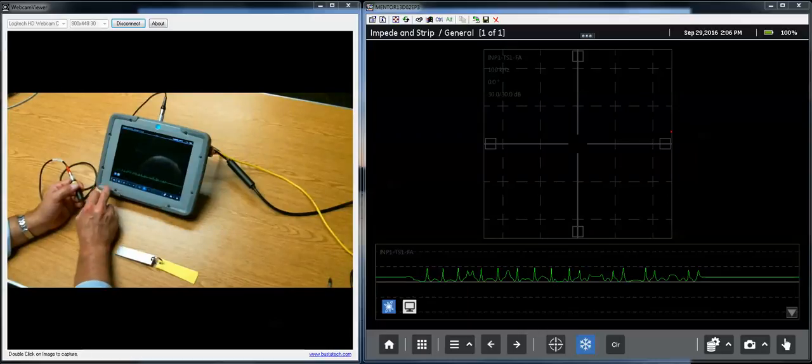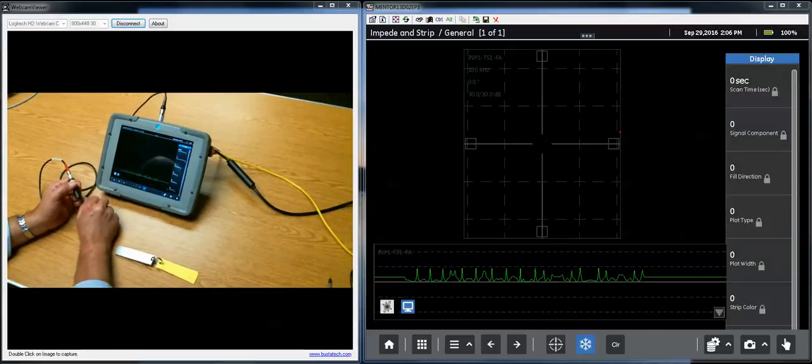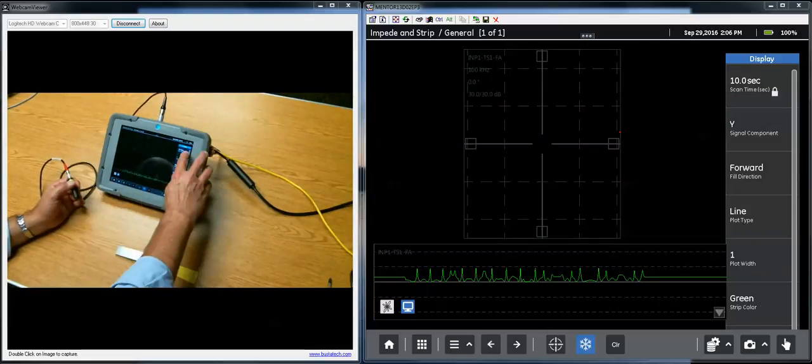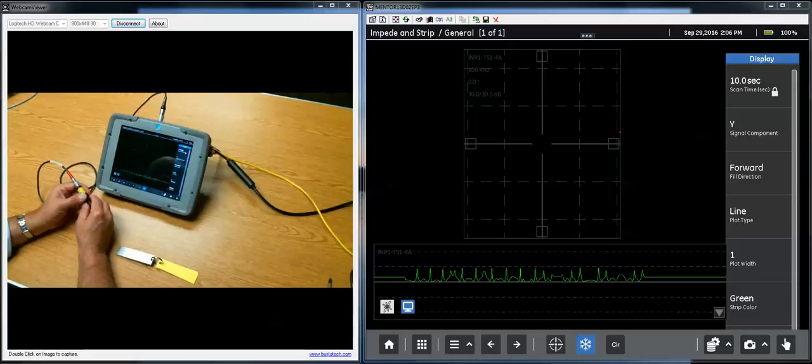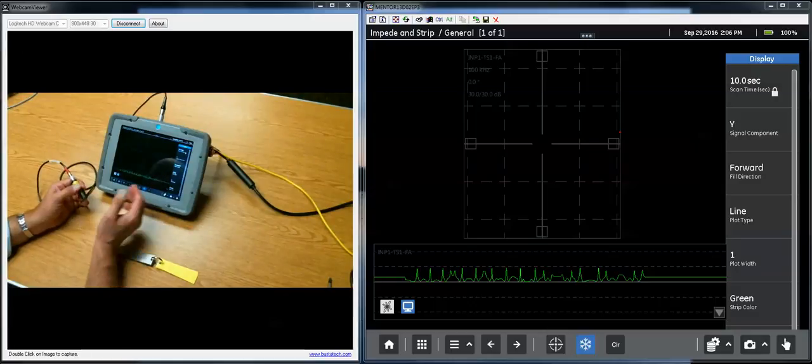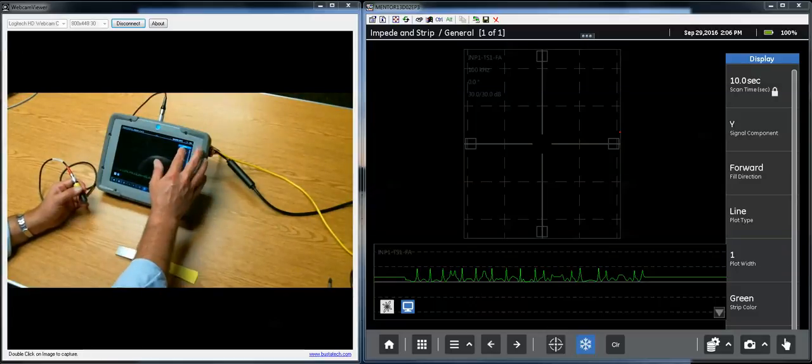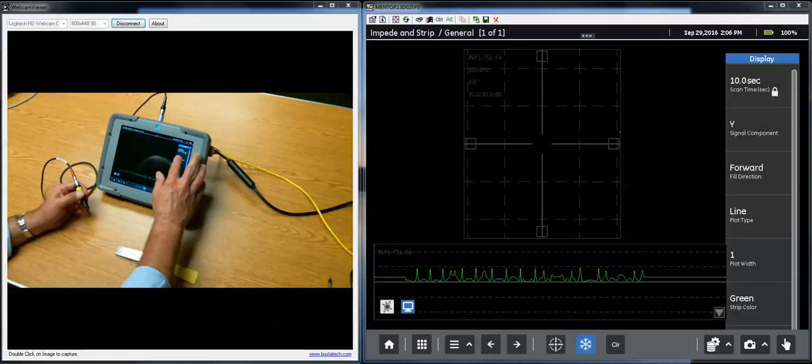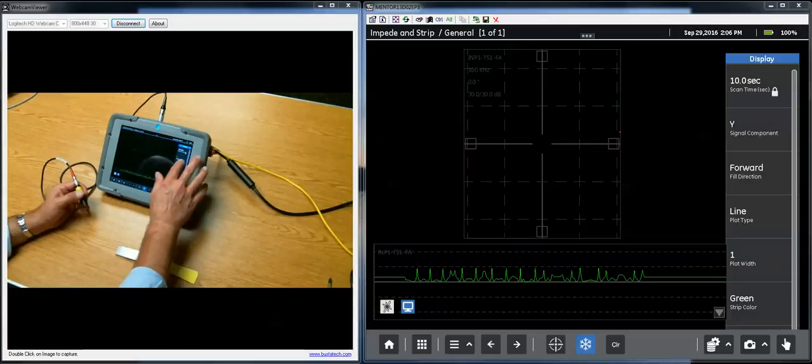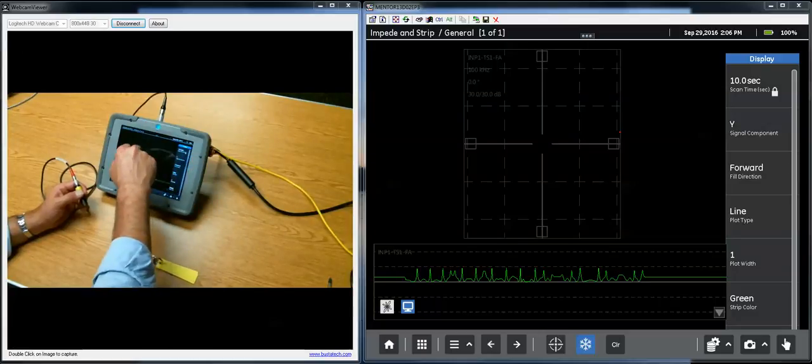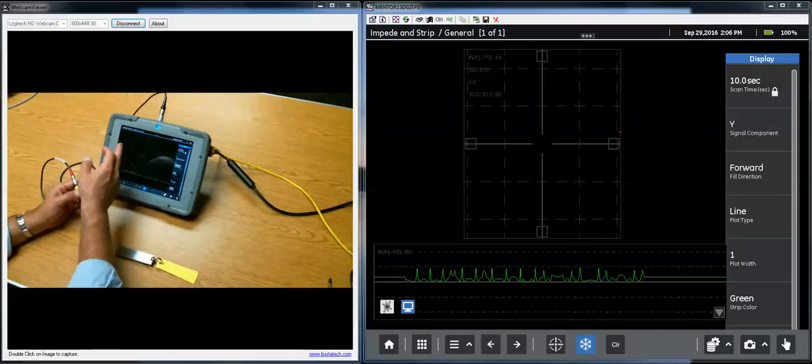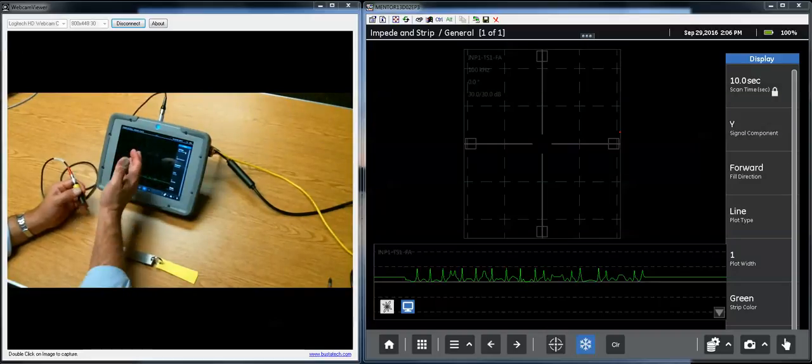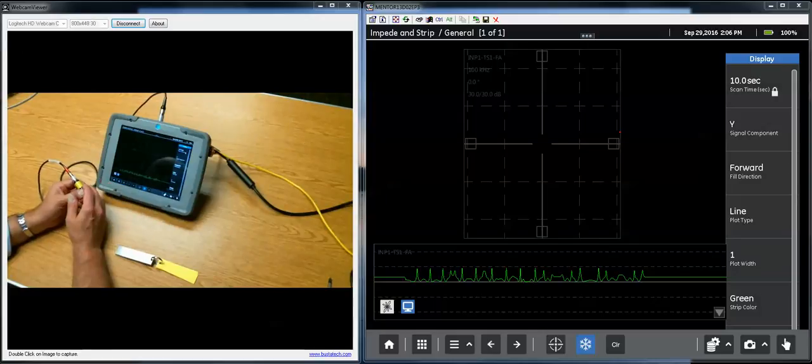If you come into the strip chart and you look at the display, the top parameter is called scan time, and that's how many seconds are displayed on the strip chart. You can set that to anything from just a little over zero to about 30 seconds. The next item that you can choose for display on the strip chart is, are you interested in looking at the Y component of the Lissajous or the X component, so you can choose which axis of indication is going to best show you what you want to see.